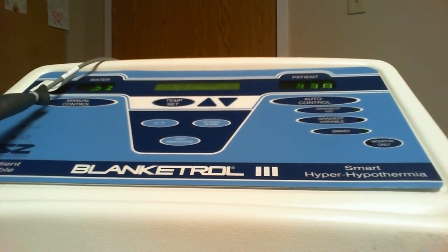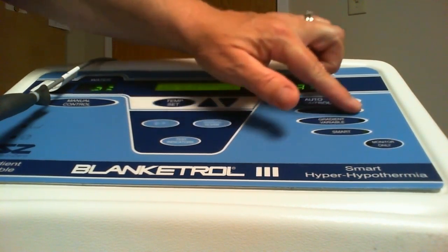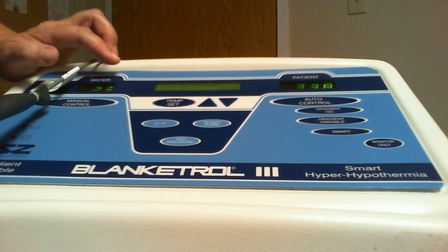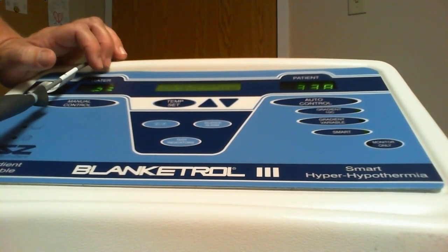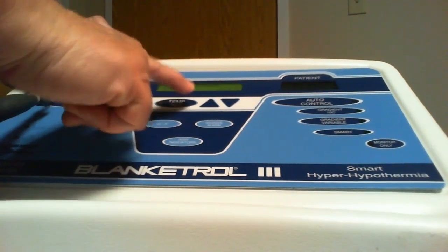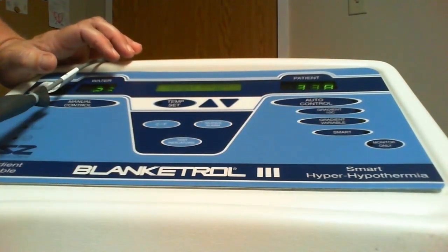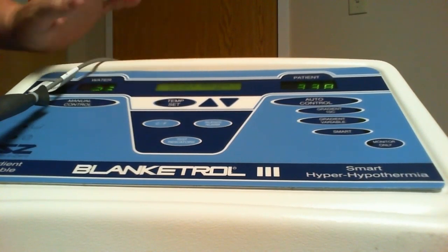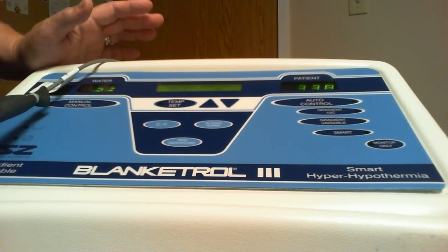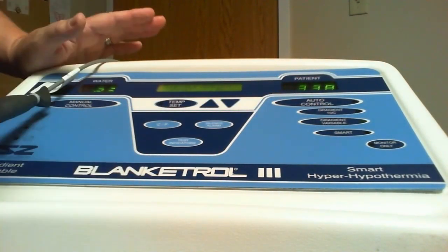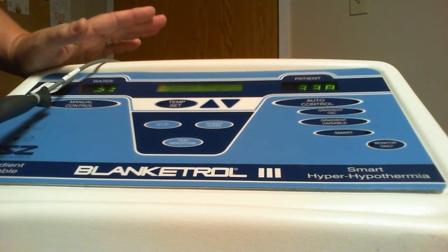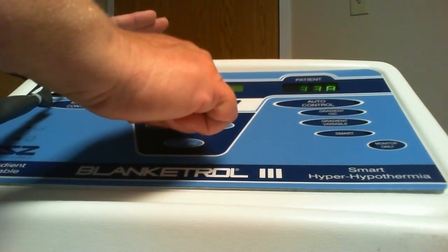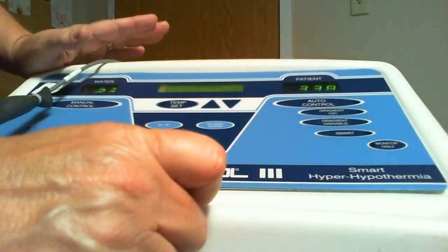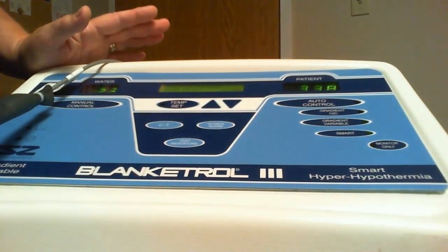Let's say we were unable to achieve target temperature in the gradient 10 mode, that the water was just not cool enough to keep the patient's temperature cold. Then I could hit temp set and go to gradient variable. And when I look at gradient variable, it says offset 0 degrees. I have to put the offset in. So in the gradient 10, it was 10 degrees difference. So let's try, we want to cool this patient a little bit more. Let's try a gradient of 15 degrees, and then hit gradient variable again. Additionally, we hit the smart mode button.